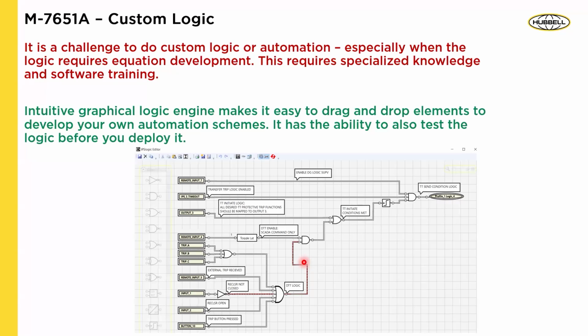And the nice thing here is you could test it. You can simulate that, hey, my remote input 7 is going to be active. What does that actually mean in terms of the output? And I can assign all of the comments, so I know exactly which signal. So if this signal is out, then I know the transfer trip initiate conditions are met. So I can attach all of these comments to it.